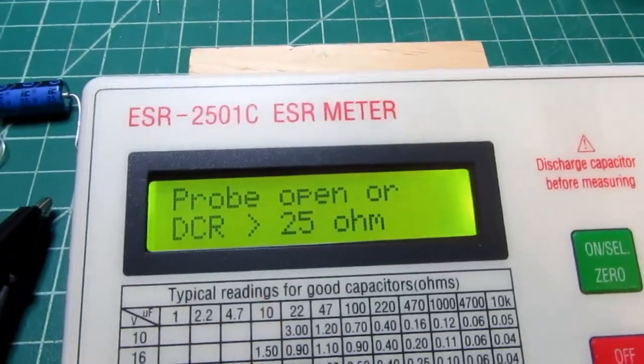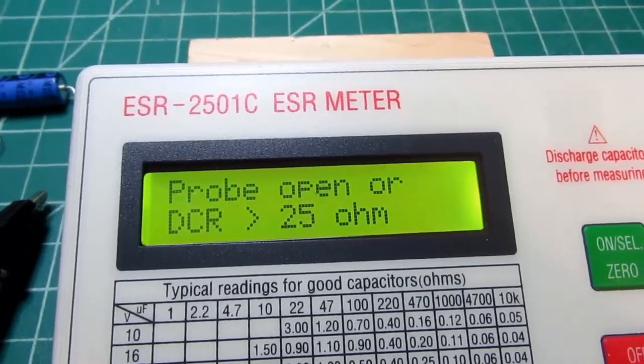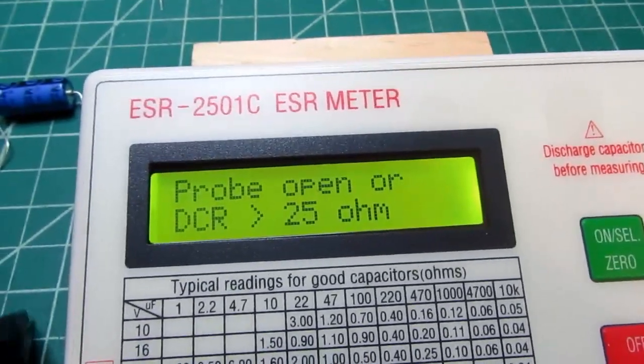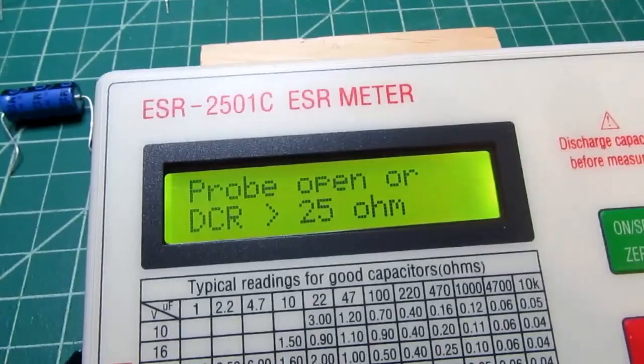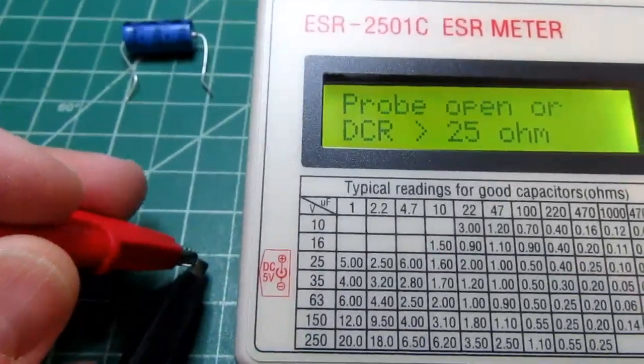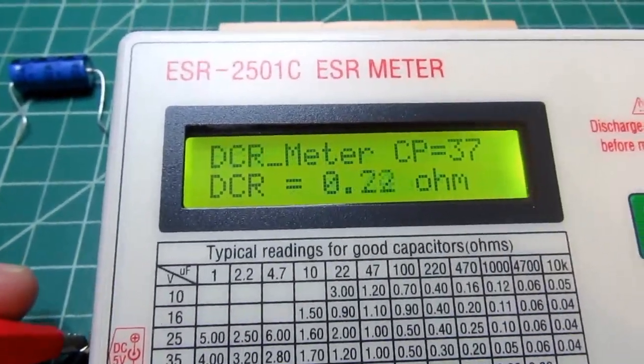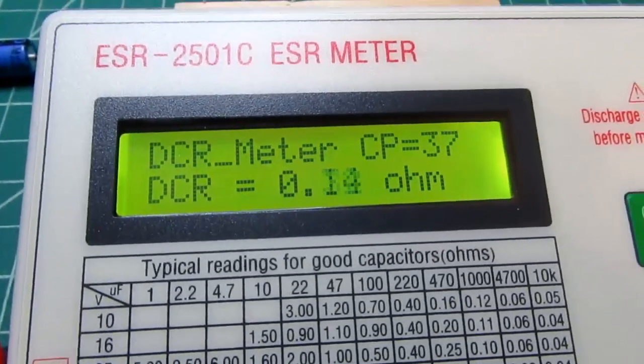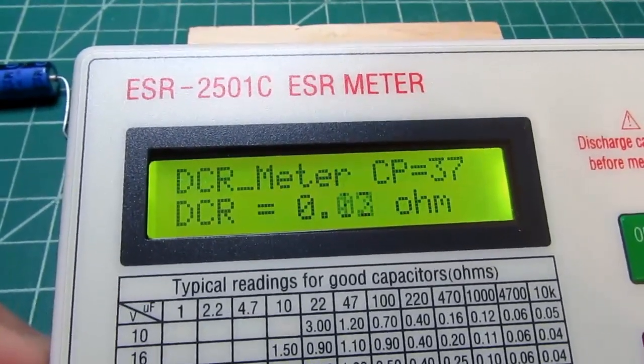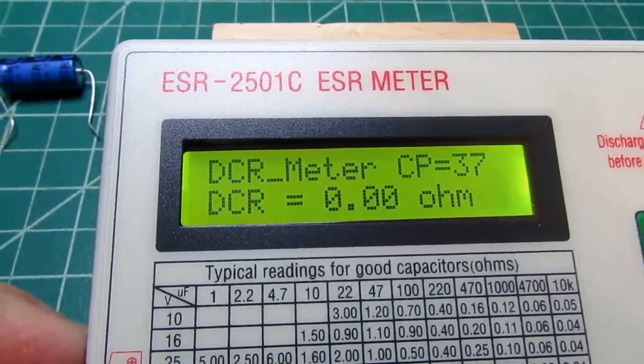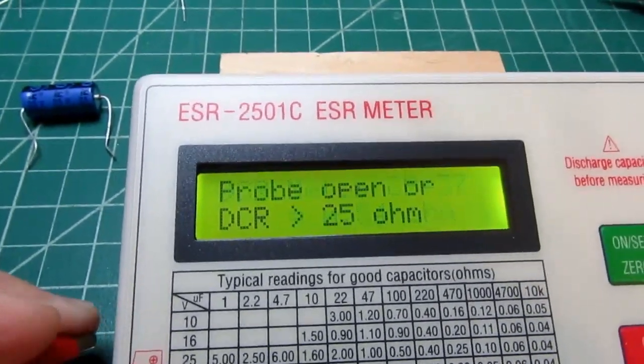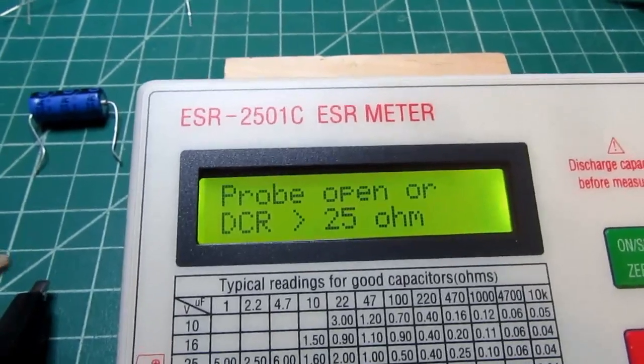So I verified that the meter thinks it's infinity, and you should always double check by shorting the probes together again and watching the display. It should go to 0 or really close to 0. If it does not do that, then do not proceed with the DCR test because it'll be invalid.